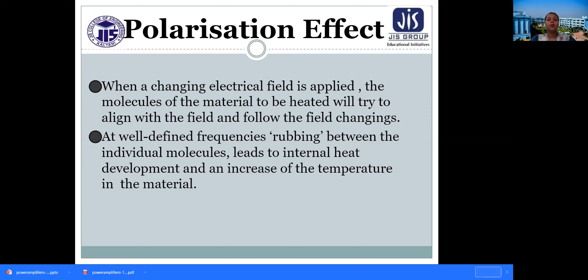How does radio frequency heating work? From this figure we can see that the power supply is connected to different electrodes, and an AC supply of 40 megahertz is applied to the heating elements. When a capacitor is connected to an AC source, practically the phase angle between the current and voltage applied is not 90 degrees. Some leakage current flows between the two plates through the dielectric medium and the power is lost. This power is utilized for heating the charge.